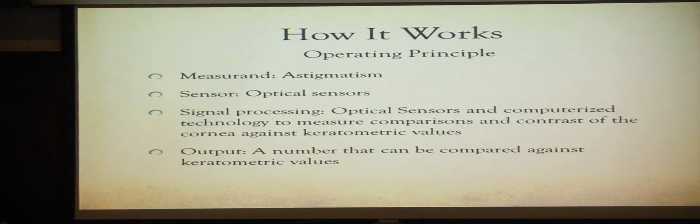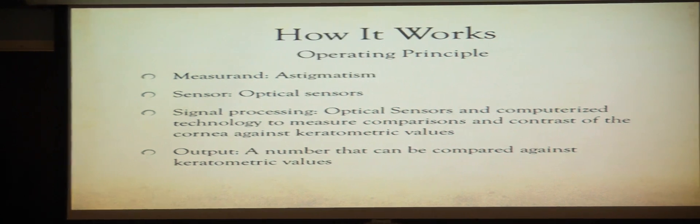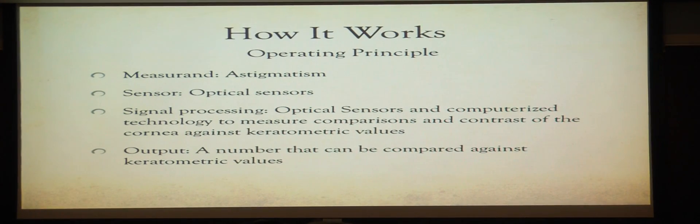How it works to measure the extent of astigmatism: the sensors are optical sensors, and the signal processing is that optical sensors and computerized technology are used to make comparisons and contrasts between the cornea against pre-known values. The keratometer actually provides a certain number, and optometrists can use this number so they'll know what the cutoff is for a normal eye versus one affected by astigmatism, and they can also determine the extent of astigmatism.